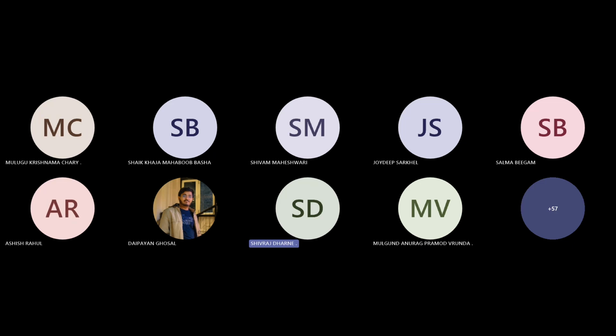So total load is 5 megawatt. So what is the IT load? What is the cooling load? And what is the miscellaneous load, like lighting, sensors, all that, right? So you can say IT load is 3.5 megawatt, cooling load is 1.2 megawatt, and miscellaneous load is 0.3 megawatt. So my total power consumption in my data center is 5 megawatt.